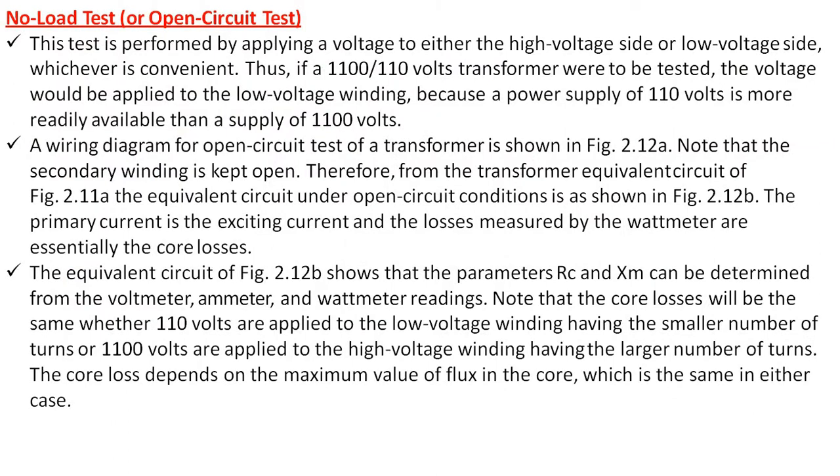The next topic, no load test or open circuit test. This test is performed by applying voltage to either the high voltage side or the low voltage side, whichever is convenient. Thus, if a 1100/110 volt transformer were to be tested, the voltage would be applied to the low voltage winding, because of power supply, 110 volts is more readily available than a supply of 1100 volts.